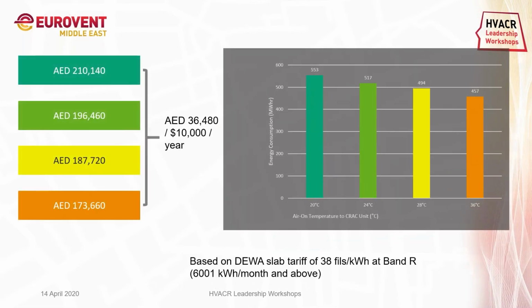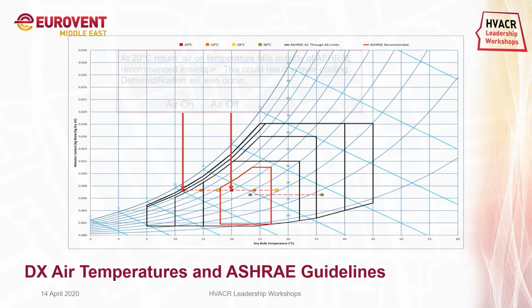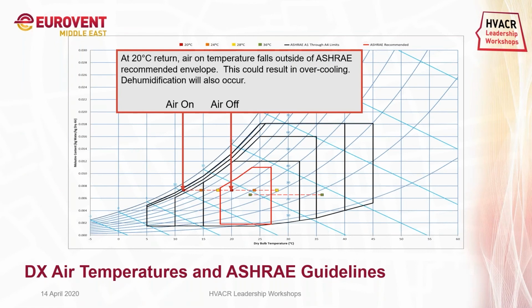We have taken the DEWA tariff and done an analysis on the cost per year. These are the costs at the four conditions, and you can see a difference of AED 36,000, which is equivalent to $10,000 per year. We are having a saving when comparing 20 degrees Celsius and 36 degree air-on temperatures. So let's see how these four conditions reflect on the ASHRAE recommended guidelines. At a return temperature of 20 degrees Celsius, you can see the air-on temperature is about 12 degrees Celsius, which is far below the recommended range of ASHRAE. This could result in overcooling. Dehumidification will also occur.